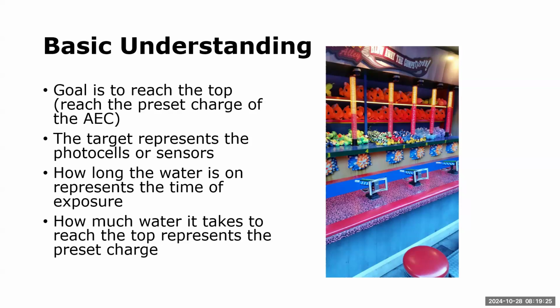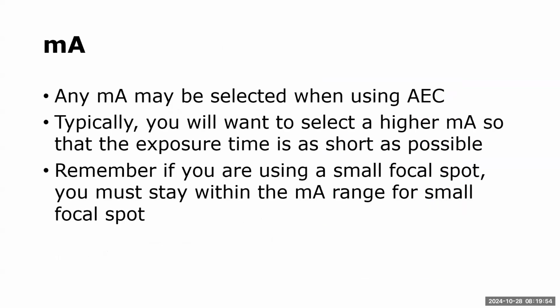You've seen those on the wall bucky, and some rooms only have 3, but some might have how many? How many have you seen out there? 5. Somebody said over here 5. So it just depends on the type of equipment that you're using. How long the water is on is going to represent the time of exposure. And then how much water it takes to reach the top represents the preset charge. So let's look at what affects how long it takes to meet that preset charge.